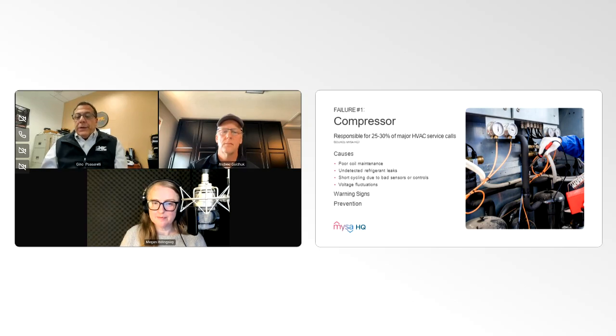How was the voltage? How was the amperage? Things of that nature. That tends to keep a tech focused on what they're supposed to be doing during either the service call or the preventative maintenance. And then another sign is, obviously, if you hear the noise factor. Generally, if you got bad bearings, or a belt is not aligned properly or damaged of some sort, it's going to be louder than typical.